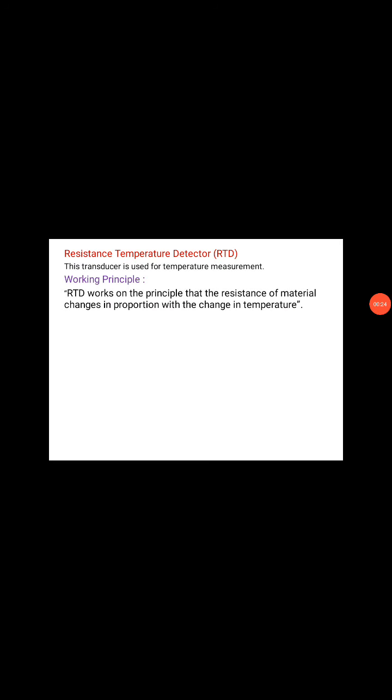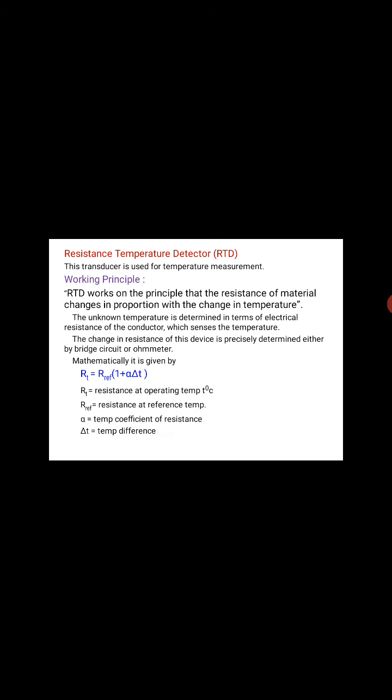Working principle: RTD works on the principle that the resistance of the material changes proportionally with the change in temperature. The unknown temperature is determined in terms of the electrical resistance of the conductor which senses the temperature. The change in resistance of this device is precisely determined either by a bridge circuit or ohmmeter.